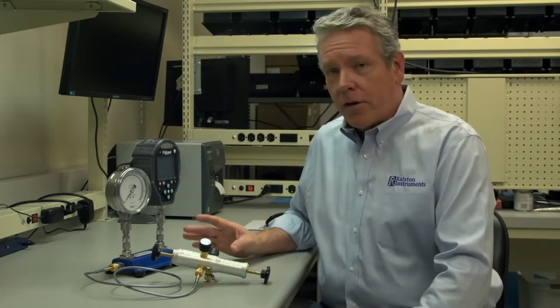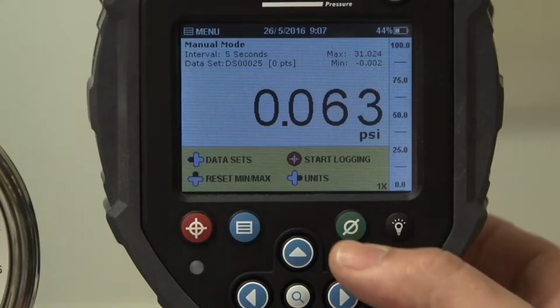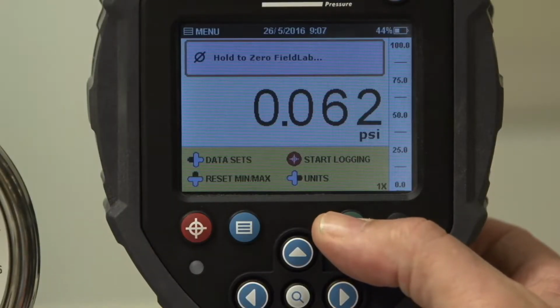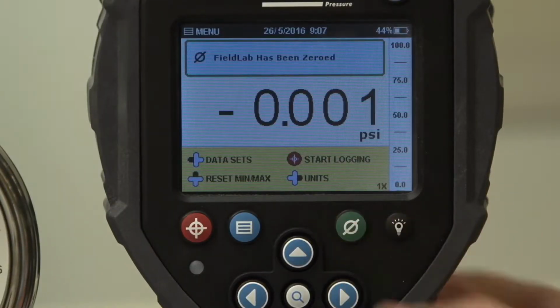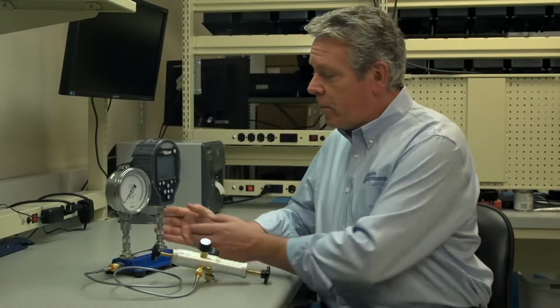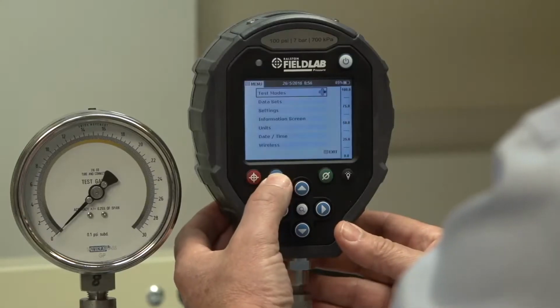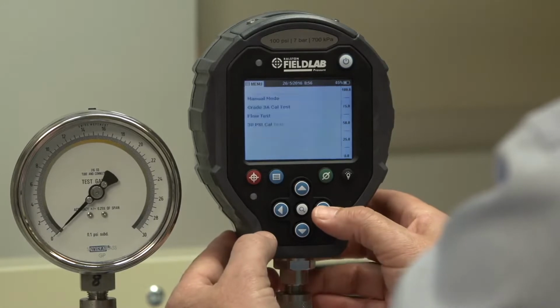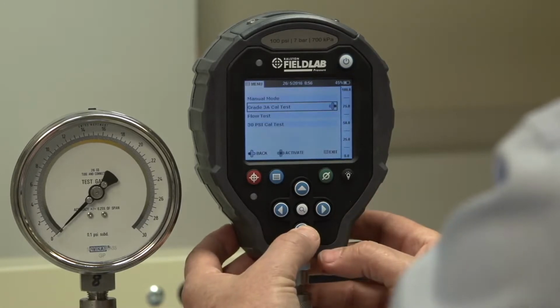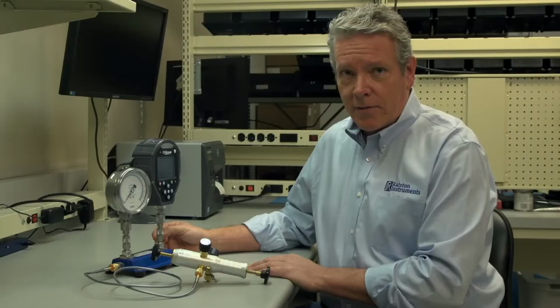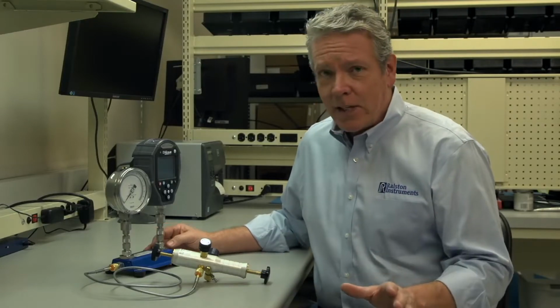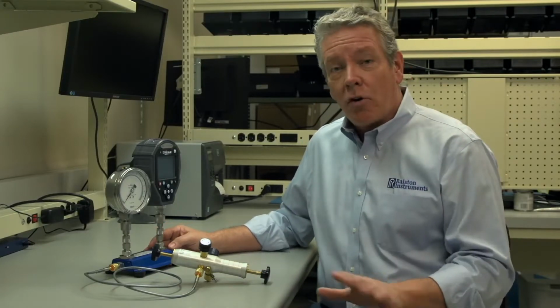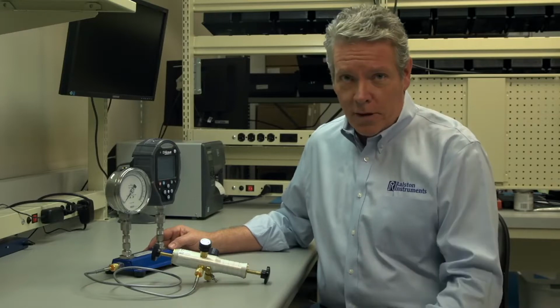Now before we start our test, we'll zero the FieldLab by pressing the green 0 button until we see the confirmation message on screen. Next, we'll press the menu button on the FieldLab to choose the test mode that we created for this type of DUT. In this case, it's the 30 psi cal test. And keep in mind that any test mode you create can be shared across your FieldLabs or with others.